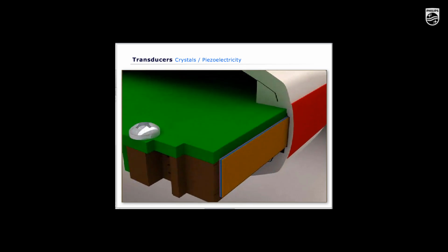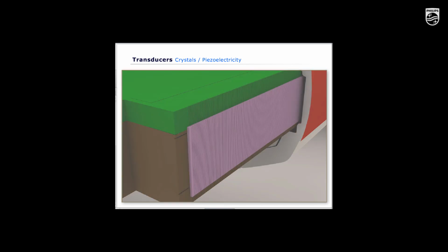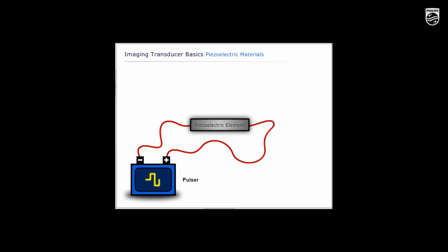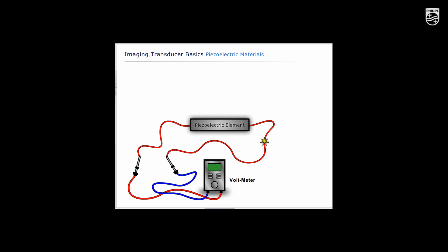Let's look at the piezo properties of ceramics in more detail. During the transmit stage, an electric voltage is applied to the face of the crystal and the crystal will deform. Depending on the polarity of the voltage, the thickness will increase or decrease. As a result of the deformity, the piezoelectric element will produce a sound wave. The terms transducer element, piezoelectric element, active element, crystal, or ceramic all refer to the piece of piezoelectric material. Ultrasound transducers typically are driven by one cycle of voltage, which produces a 2 or 3 cycle ultrasound pulse. The frequency of the sound produced is equal to the frequency of the driving voltage, which must be near the operating frequency or so-called resonance frequency.